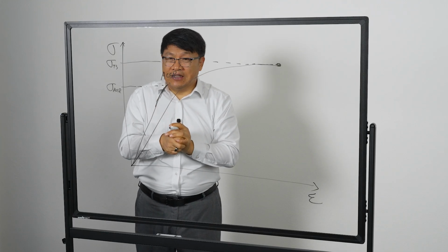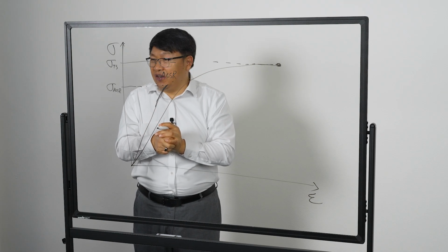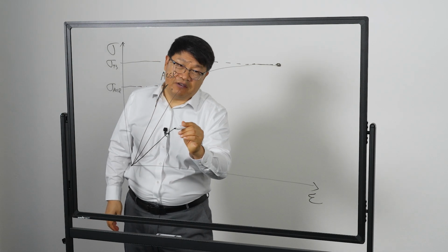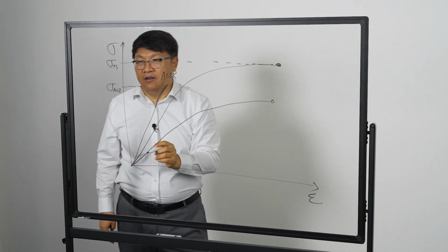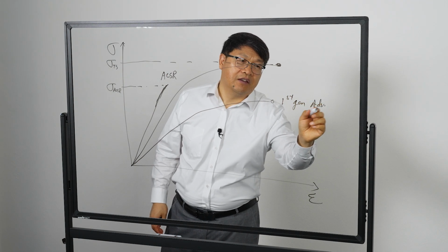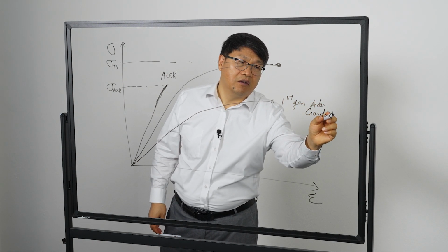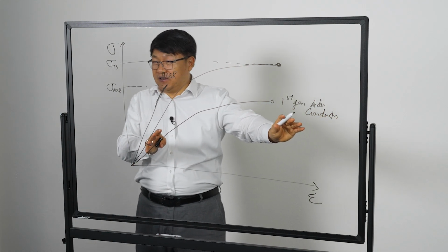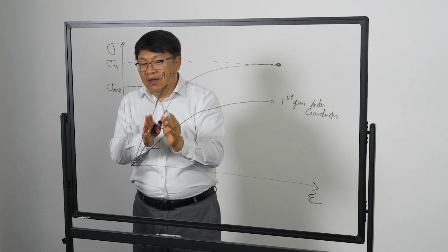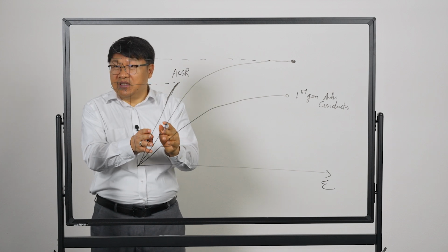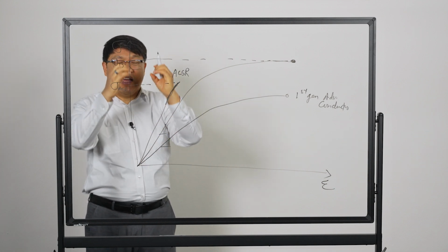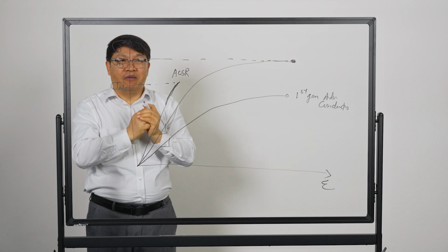If you were to look at some of the, let's say, earlier generation advanced conductors, the modulus is a little bit less. The curve might be a little bit different. I would say first gen advanced conductor. Why? The aluminum may behave similarly, but the composite core, if I look at the slope, has a lower value, which is the modulus, simply because when you have a lot of fiberglass in it, it robs down the modulus of the carbon fiber composite.